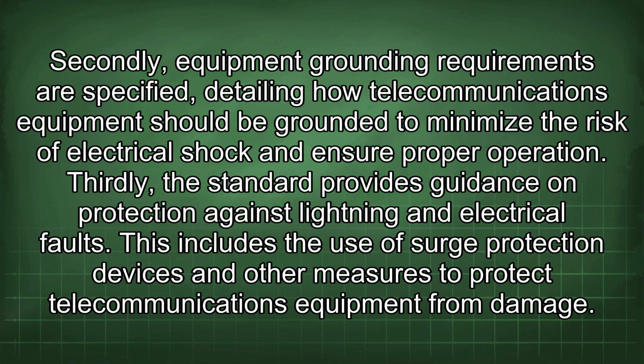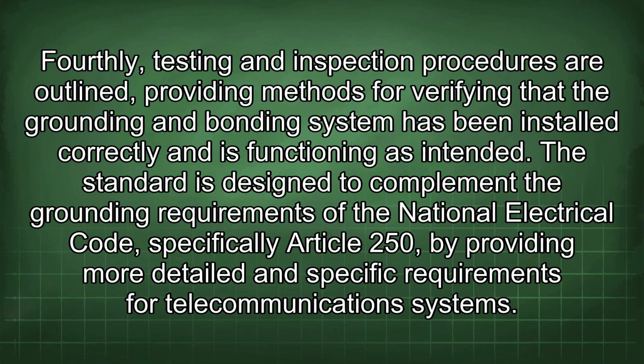Secondly, equipment grounding requirements are specified, detailing how telecommunications equipment should be grounded to minimize the risk of electrical shock and ensure proper operation. Thirdly, the standard provides guidance on protection against lightning and electrical faults. This includes the use of surge protection devices and other measures to protect telecommunications equipment from damage. Fourthly, testing and inspection procedures are outlined, providing methods for verifying that the grounding and bonding system has been installed correctly and is functioning as intended.